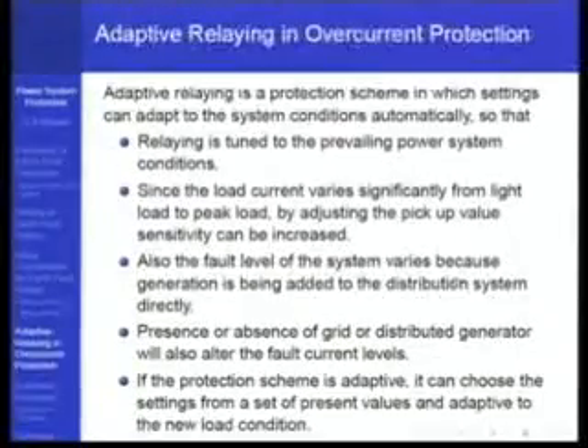Okay. I think a quick note on adaptive relaying. Basically, system conditions change throughout the day, load conditions change throughout the day. So if you want to make your protection more effective than giving one setting for a whole day or a whole year, you could actually have, with a computer relay, a lookup table, and according to the changing systems or times, or feeders in service, not in service, you could change the pickup setting through a lookup table.